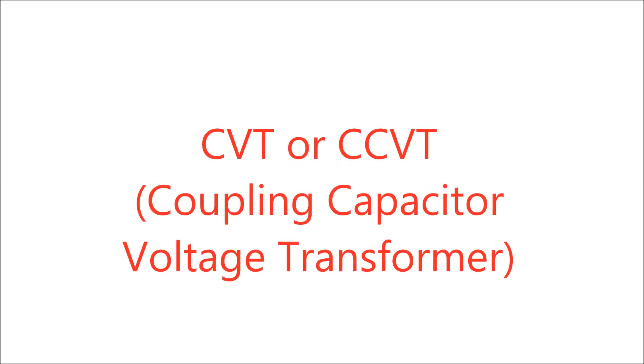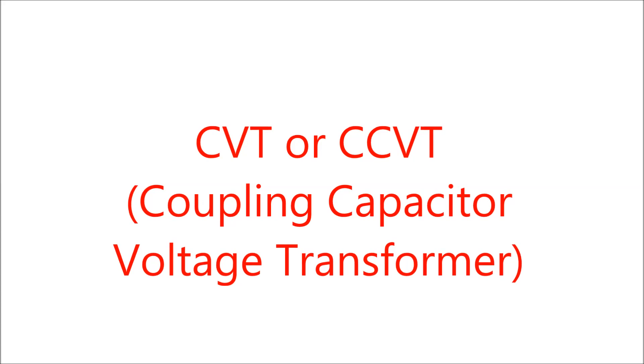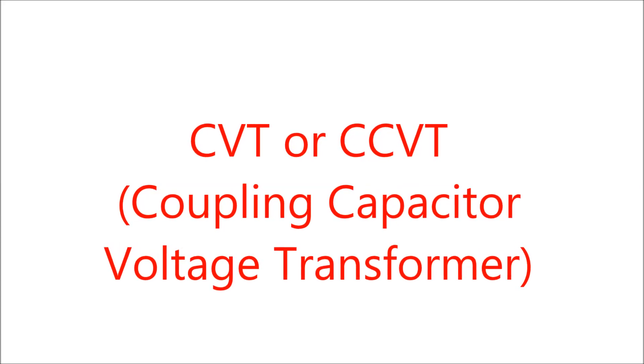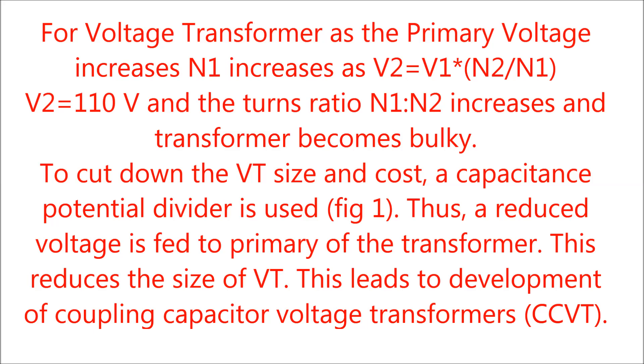CVT, or practically called CCVT (Coupling Capacitor Voltage Transformer), has a secondary voltage of 110 volts for VT. If we increase the primary voltage beyond 132 kV, we have to increase the number of turns N1 by N2, which will make the transformer more bulky and less cost-effective.